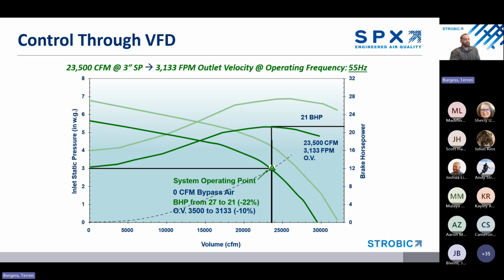So when demand is low, the controller slows the fans within the safe limitations of the system. And when conditions change, it ramps them back up, eliminates bypass flow, and maintains proper plume dispersion safety. The real big advantage here is that the controller is going to minimize or eliminate the need for bypass air when feasible, right? So instead of exhausting extra ambient air, it uses smart system modulation to get the same safe plume height with less airflow. So that's going to result in lower fan horsepower, reduced heating and cooling loads, and it's going to translate to an overall energy savings.